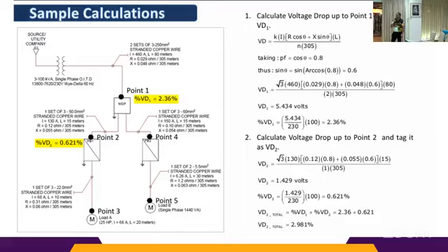The power factor is 0.8. Substituting in the formula, voltage drop 1 is 5.434 volts, so the percent voltage drop 1 is 2.36%. Now for the voltage drop to Point 2, let's call it voltage drop 2. We have the resistance and reactance, and substitute them in the formula. Voltage drop 2 is 1.429 volts, and the percent voltage drop 2 is 0.621%. The total is 2.36 plus 0.621, so the voltage drop 2 total is 2.981%.